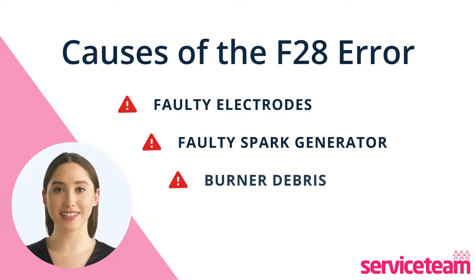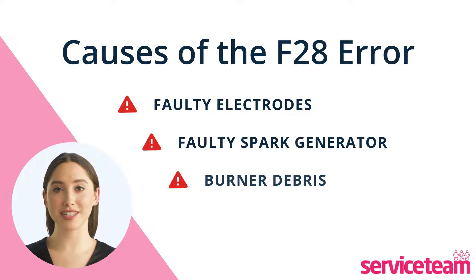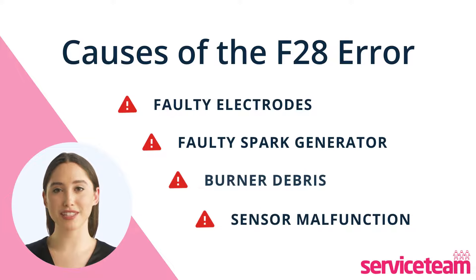Burner debris in a boiler is another cause for the F28 fault code. Even a small amount of debris, such as carbon buildup, can block the burner and prevent ignition. Additionally, boiler sensors are essential for safety and efficiency — an F28 issue could indicate a malfunction in the temperature sensor, causing inaccurate readings needed for ignition or potentially faulty sensor wiring.